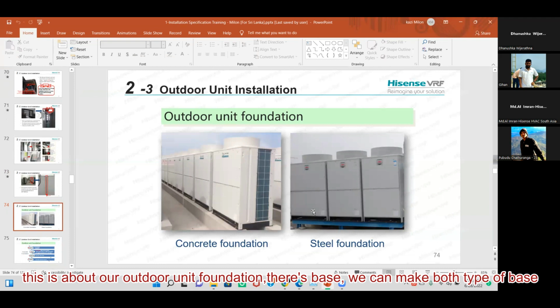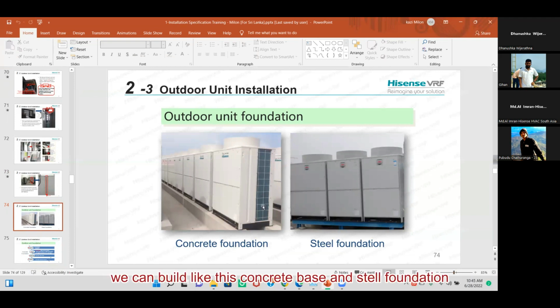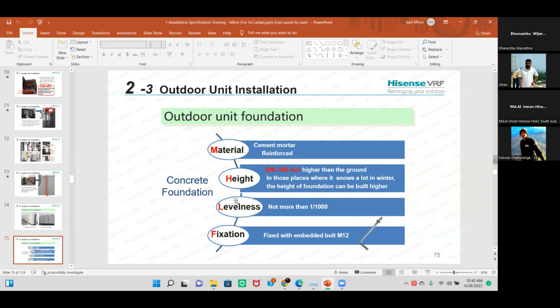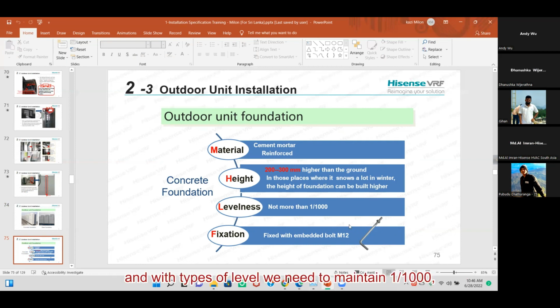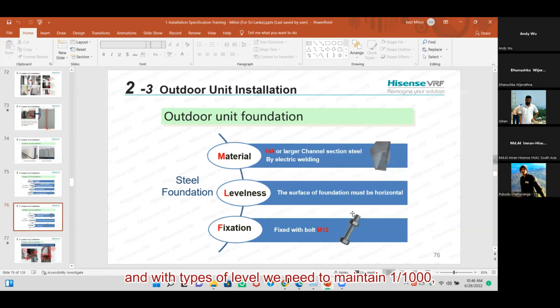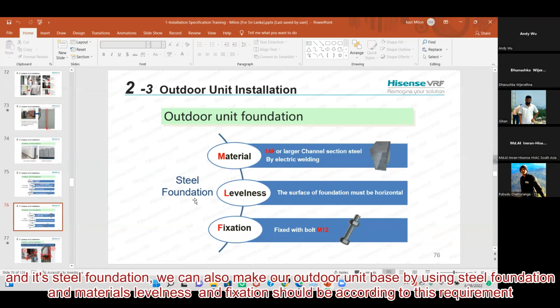This is about our outdoor unit foundation. That's the base. We can make both types of base. We can build a concrete base or a steel foundation. This is our concrete base. If we use a concrete base, then we need to consider which type of material we need to use, and the height should be 200 to 300 mm, and levelness, and these types of issues we need to maintain. And for a steel foundation, we can also make our outdoor unit base with steel. The materials, levelness and fixation should be according to this requirement.